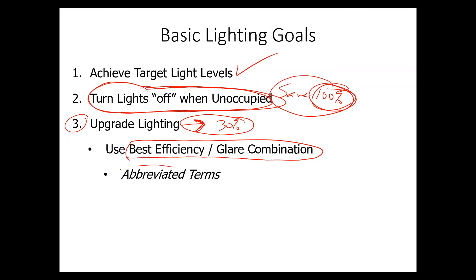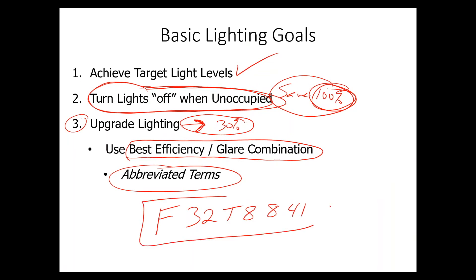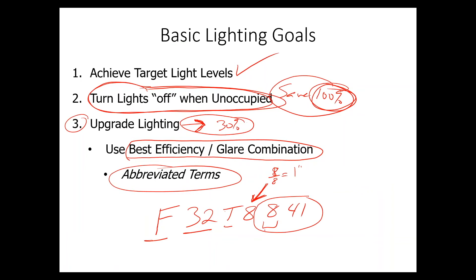Let me go through some abbreviated terms common in the lighting industry. Here's something you might see on the side of a lamp: the F means fluorescent, the 32 is the watts, T means tube, and 8 means eighths of an inch — so this would be eight-eighths of an inch, or one inch in diameter. The last three digits are actually two different things: the 8 refers to the CRI (color rendering index), and the 41 indicates the color temperature is 4100 Kelvin. If you see that on the lamp in the ceiling, you'll know how to do the retrofit to accomplish what you're trying to achieve.